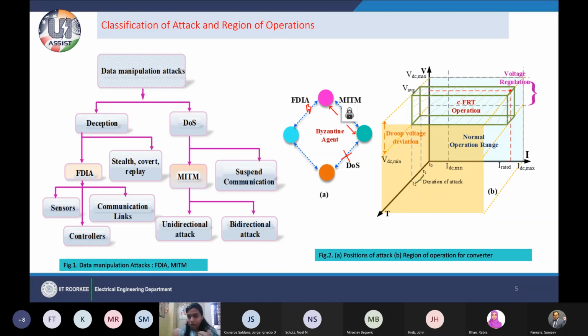And now the operation which I would like everybody to focus on is the communication fault ride-through operation. It is different from physical fault ride-through, because for physical fault ride-through identification, the indices are different and the operational action taken is different. For communication fault ride-through, we actually analyze the information and decide whether we can provide some trade-off and let the converter sit there until the thresholds are violated. That is, Vmax and IDC max are violated. Next slide.